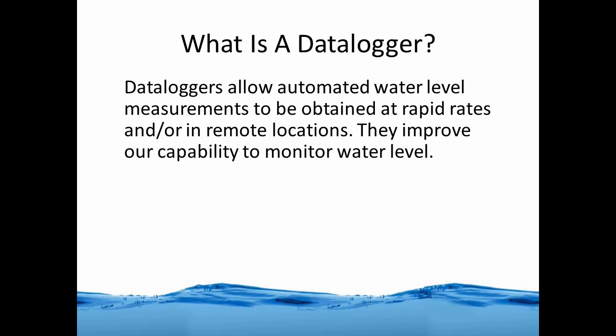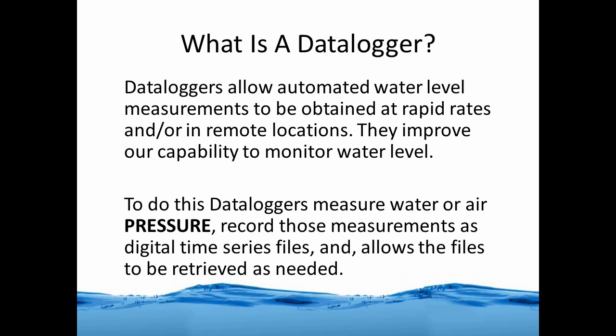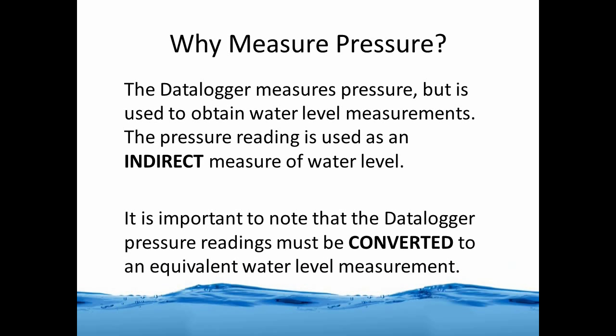To do this, data loggers measure water or air pressure and record those pressure measurements as a digital time series file, then allow these files to be retrieved as needed. Why measure pressure? The data logger measures pressure because it's used to help determine a water level measurement. The pressure reading is used as an indirect measure of water level, and it's important to note that the data logger pressure readings have to be converted to an equivalent water level measurement.